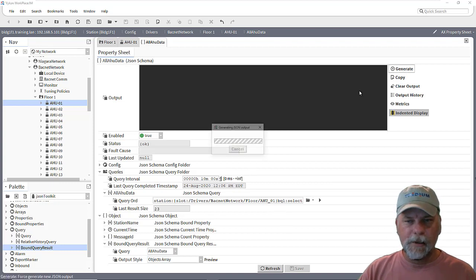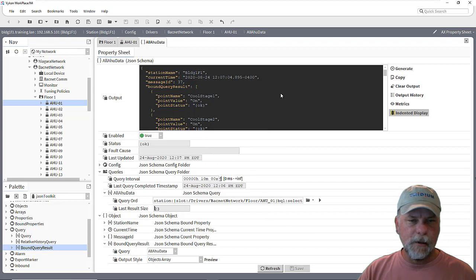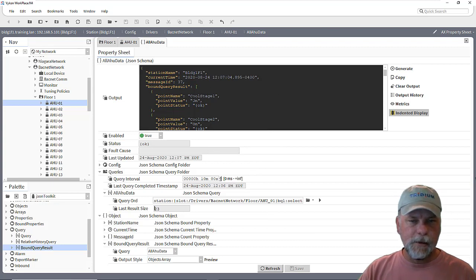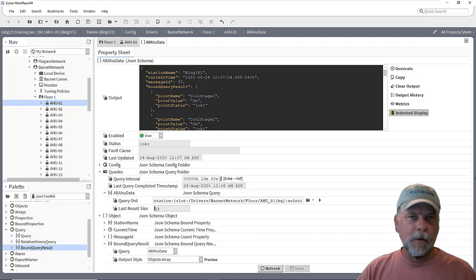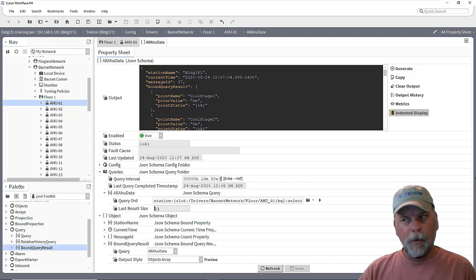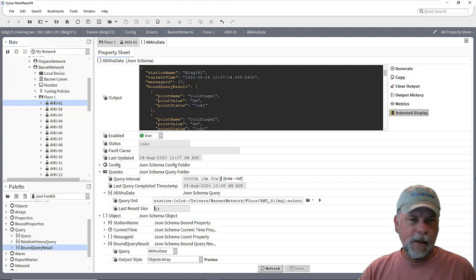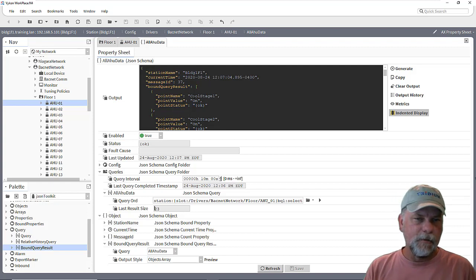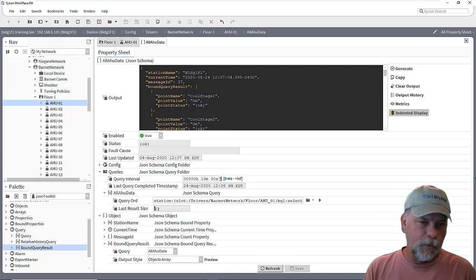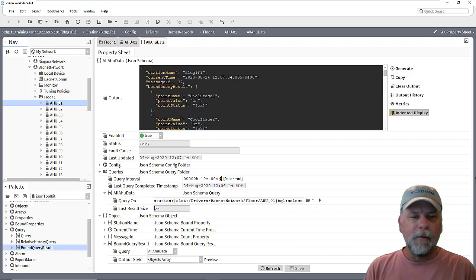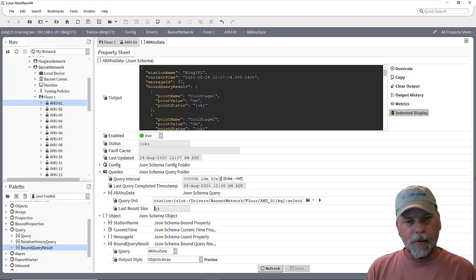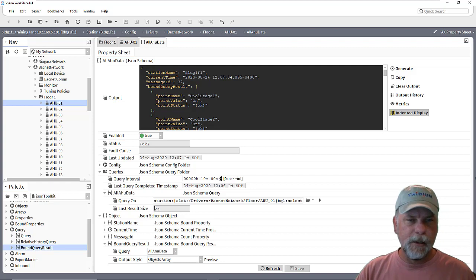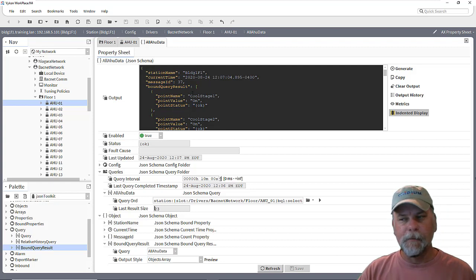When I generate the JSON it's only going to be showing the point data from AirHandler 1. So this would let me be a little more granular about the information I'm publishing. Instead of publishing one message with point data for 285 points, maybe I'm publishing a message per device with just 23 points or whatever it might be under the device.